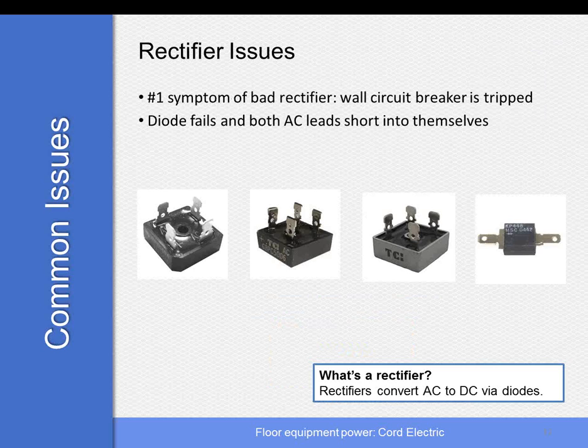Rectifiers. I discussed rectifiers briefly in the beginning. A rectifier will convert AC to DC power via diodes. Without getting too complicated, AC is a waveform, DC is a straight line. A rectifier knocks off one peak of the wave and then flips it over. So when you have a bad rectifier, number one symptom you're going to see is a wall breaker will trip.